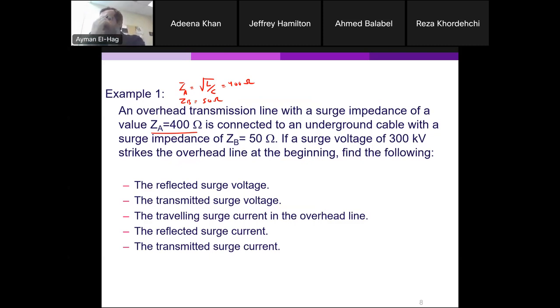And you see this configuration a lot. For example, in distribution systems, inside the city, you see overhead lines, and then if you have a pad-mounted transformer, there will be a cable coming from the overhead lines to the underground cable. So that is basically the termination. Here, this is the junction. And this junction would basically be the weakest point, for a couple of reasons. One of them is that this junction or cable termination is done in the field, not in the factory. So it is prone to a lot of defects, especially because of the environment, because of how skilled your worker is, and also because of the surge that happens at this junction point, as we will see. So usually when there is a fault in underground cables, this is one of the weakest points.